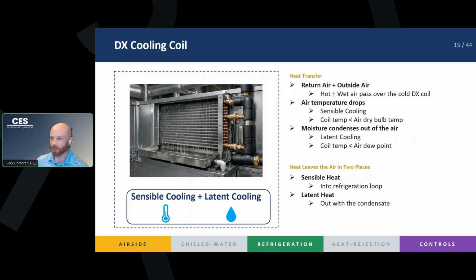So, when our return and our outside air mix, they're going to pass over the filters. They're going to then pass over this coil, right? As hot, wet air passes over a cold coil, you're going to drop your air temperature, right? That's our sensible cooling. And we're going to condense the moisture out of the air, right? That's our latent cooling. This coil is going to allow us to achieve the temperature and the humidities that we want in our space, just by nature of having the intersection of our two loops here.